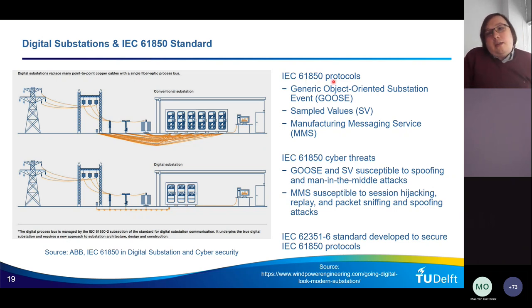And this standard has multiple protocols like GOOSE, that stands for Generic Object Oriented Substation Event, SV, that stands for Sample Values, and MMS, that stands for Manufacturing Messaging Service.